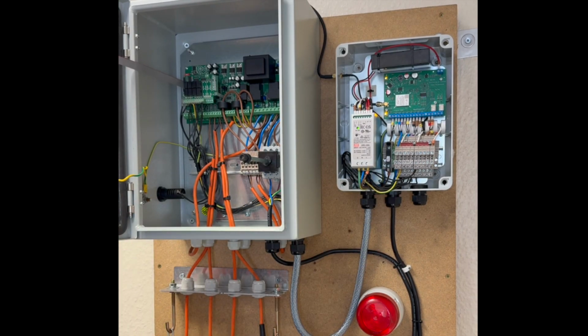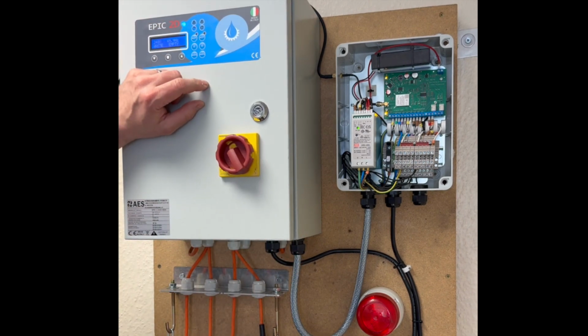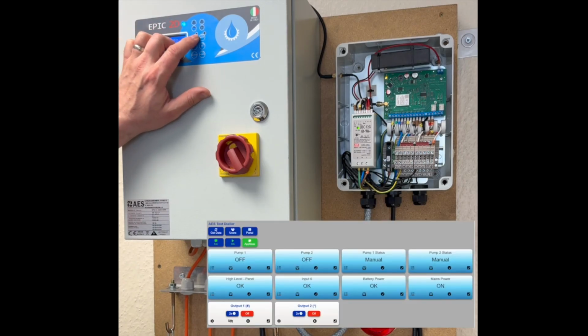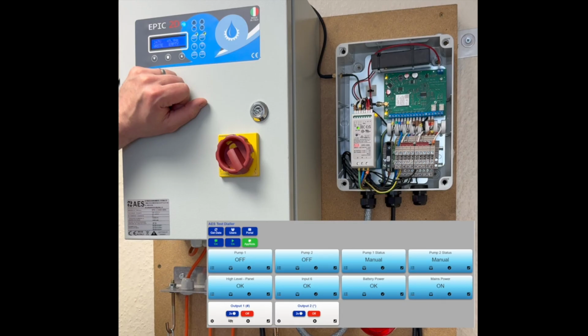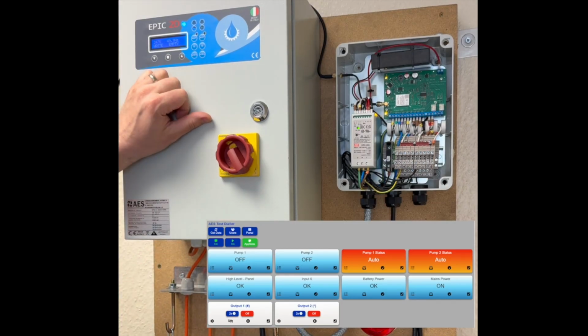But for this video, because we've now got that connected on our BMS board, if you look down on the right hand side, when we put them both in auto, you can see the status change on the portal, so you can see that the pumps are in that position. It also gives you a record of when that happened, so if the maintenance man has come in and switched your pumps onto manual, then you can track exactly when that happened. If I put them back into manual, you can also see that going back on the portal as well.